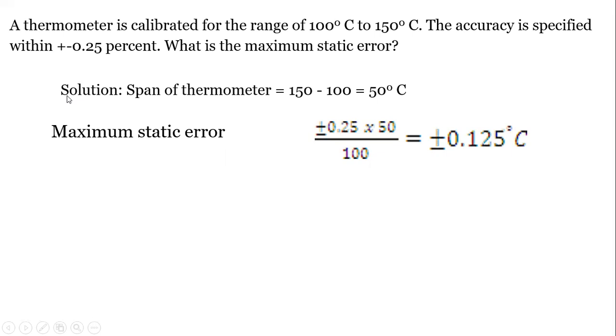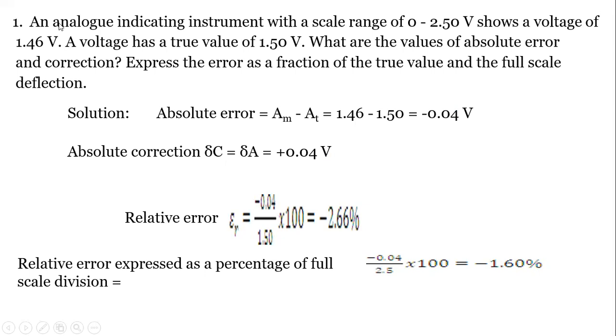Example: A thermometer is calibrated for a range of 100°C to 150°C, with accuracy specified as ±0.25%. The span is 150 − 100 = 50°C. The maximum static error is ±0.25 × 50 / 100 = ±0.125°C, which is applicable over the entire span of the instrument.